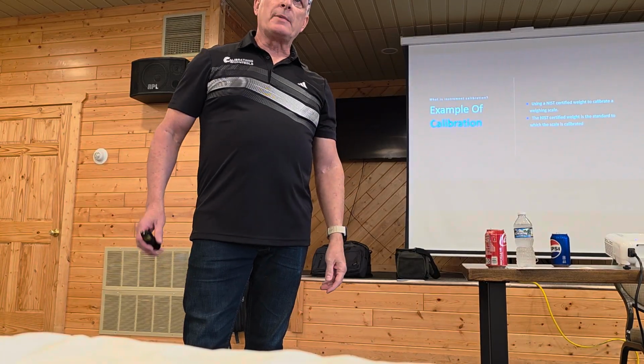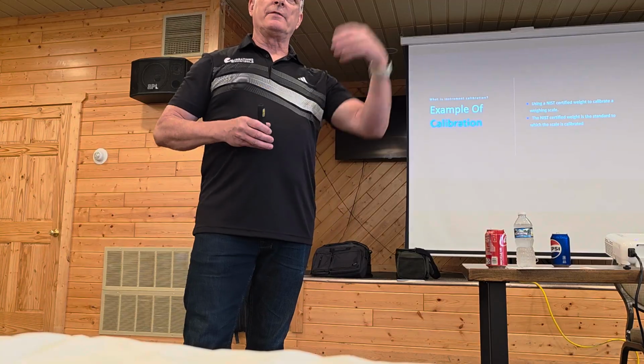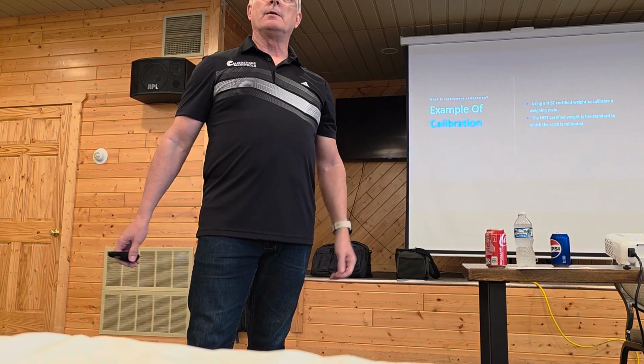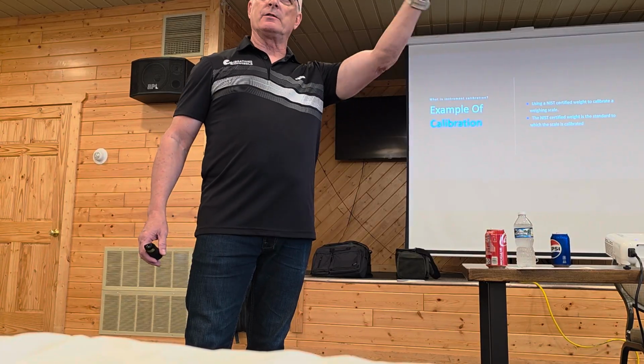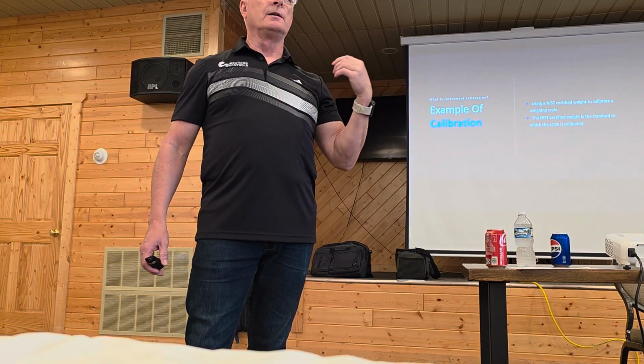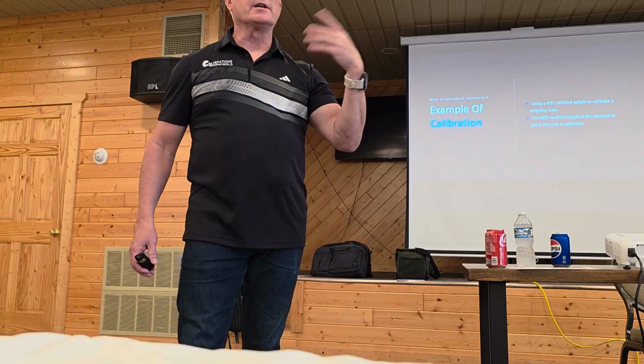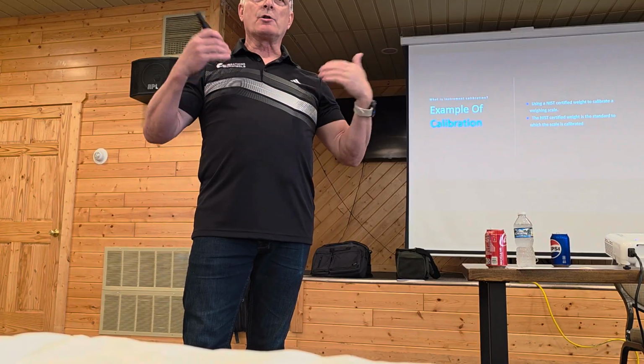The verificators for the mag meters we have to buy from the manufacturer. They've got the testing to make sure that thing's right, and we can test it in the plant. Our meters we send in, and they've got the standard. They compare our 4 to 20, make sure it's right on. 1 to 4 volts, 1 to 10 volts, whatever. They make sure our equipment's right.